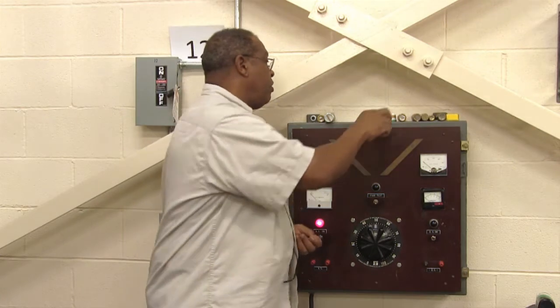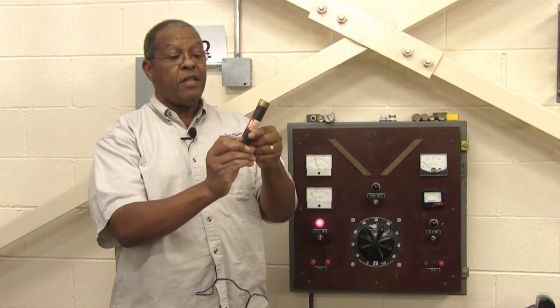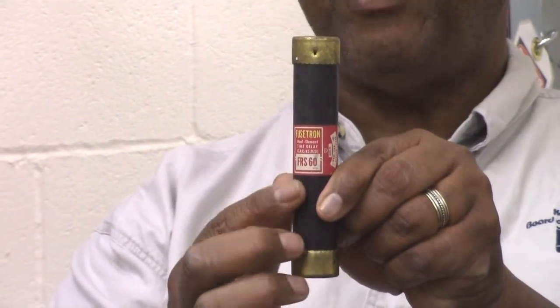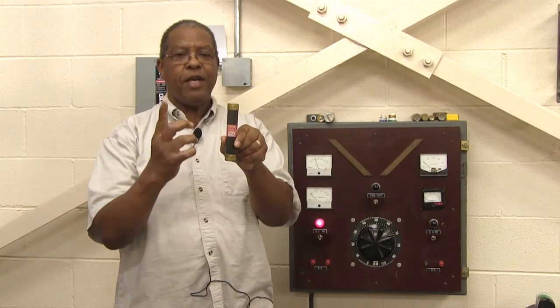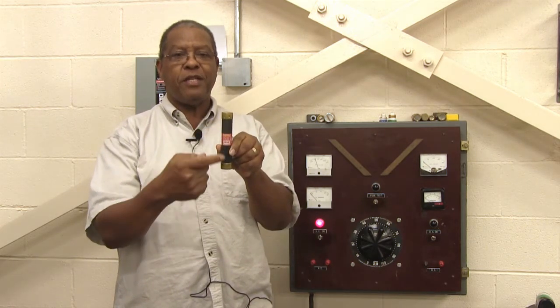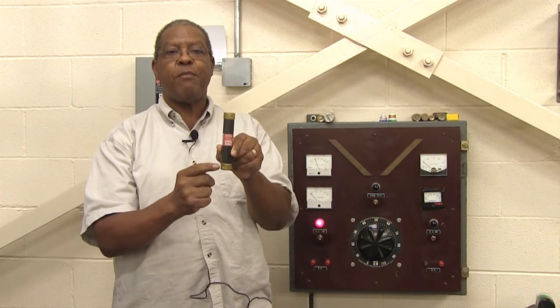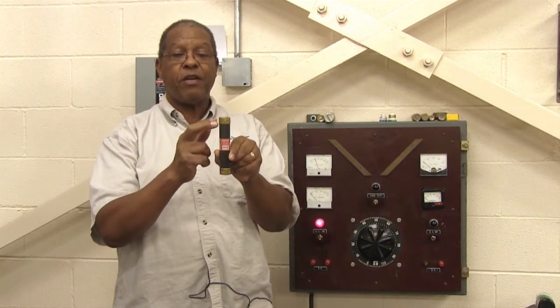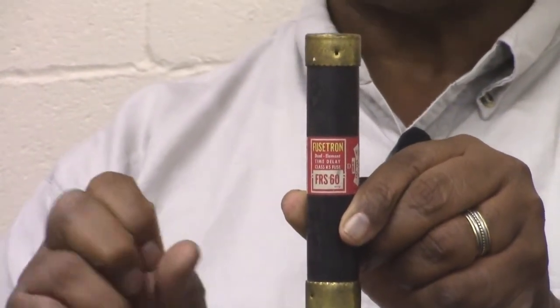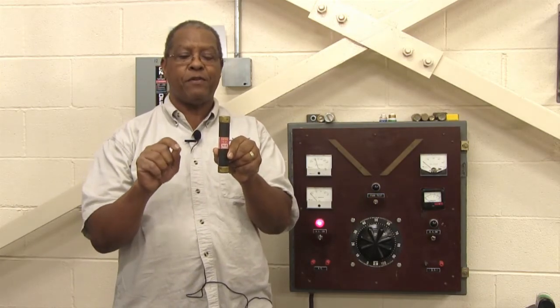The next fuses are all pretty much the same size — ferrule type fuses — but as you can see, the amperage on this one is 60 amps. You're getting into much heavier equipment when you use a 60 amp fuse. You can never determine if this fuse is good or bad just by looking, because you can't see the fuse link inside, which connects the circuit and senses how much current is flowing. When that current is exceeded, the fuse will blow to protect the wires from burning and prevent a fire or equipment damage.